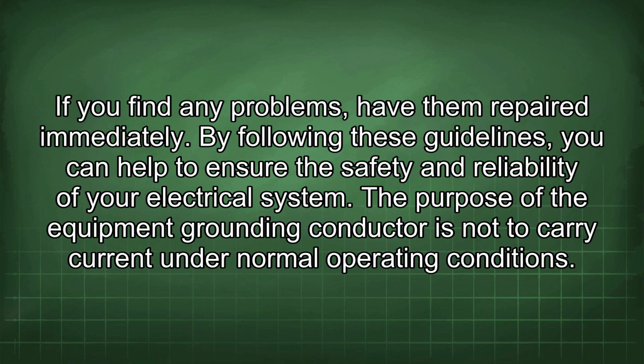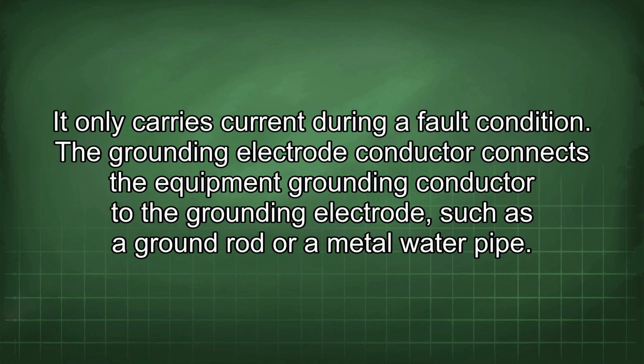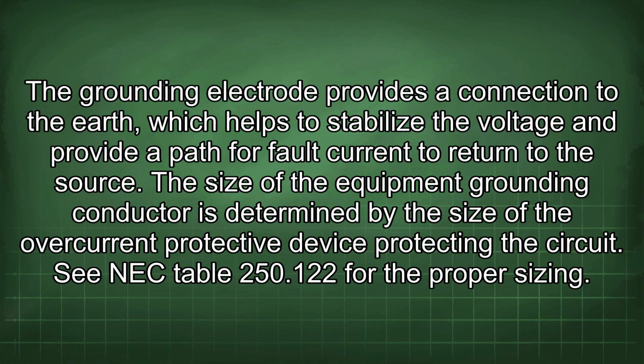The purpose of the equipment grounding conductor is not to carry current under normal operating conditions. It only carries current during a fault condition. The grounding electrode conductor connects the equipment grounding conductor to the grounding electrode, such as a ground rod or a metal water pipe. The grounding electrode provides a connection to the earth, which helps to stabilize the voltage and provide a path for fault current to return to the source. The size of the equipment grounding conductor is determined by the size of the overcurrent protective device protecting the circuit. See NEC Table 250.122 for the proper sizing.